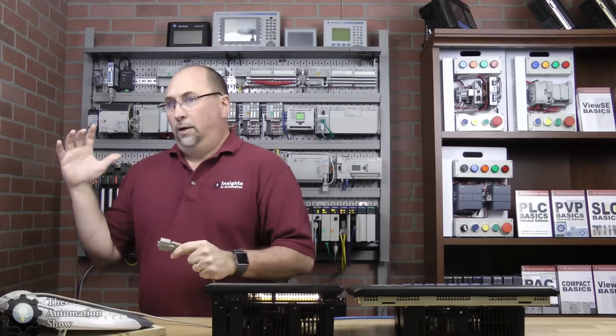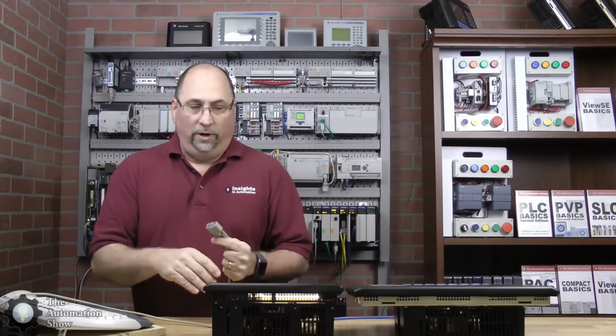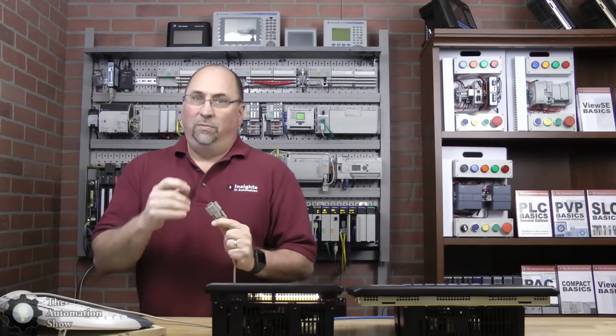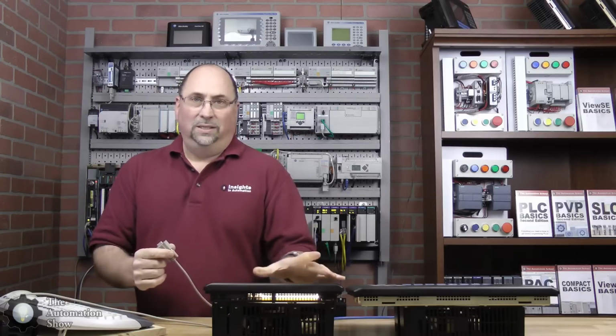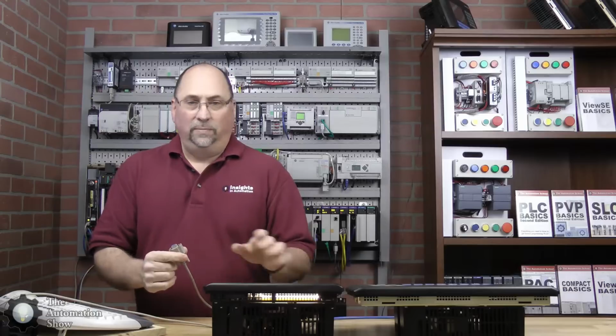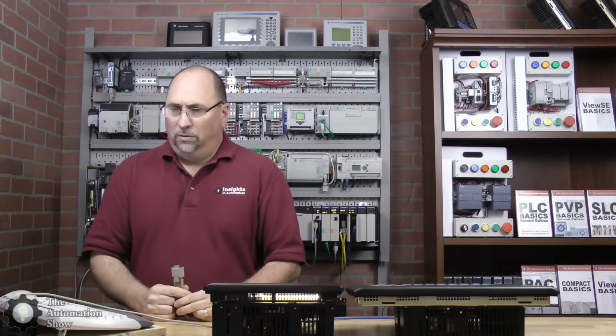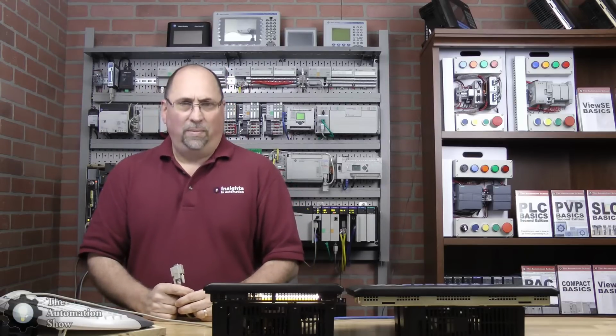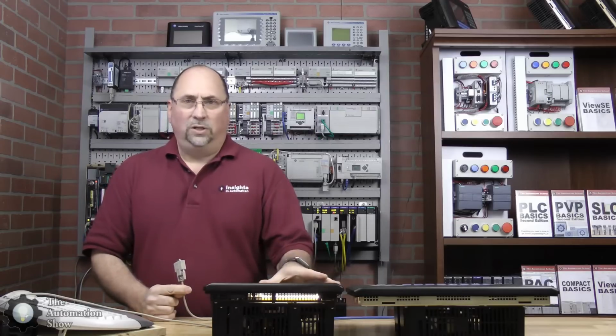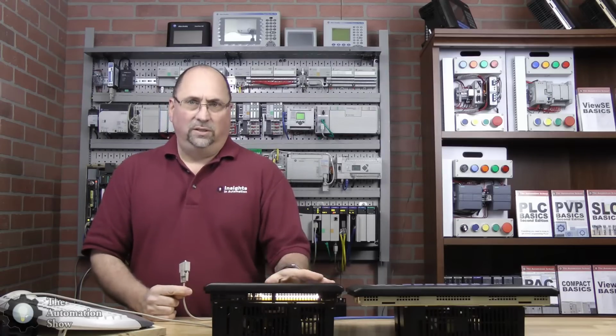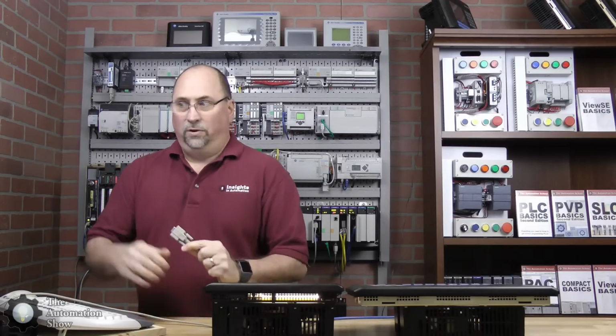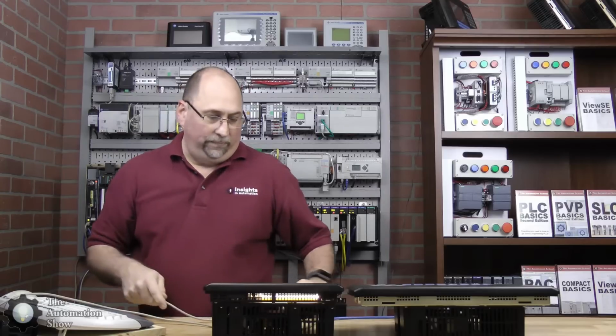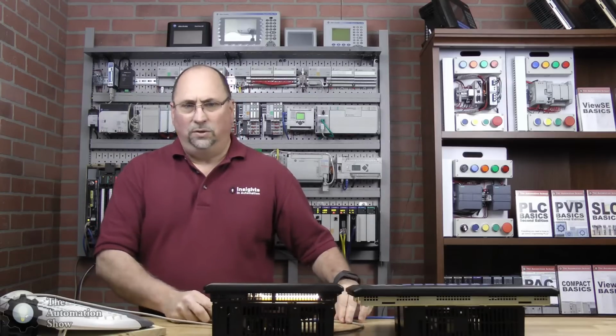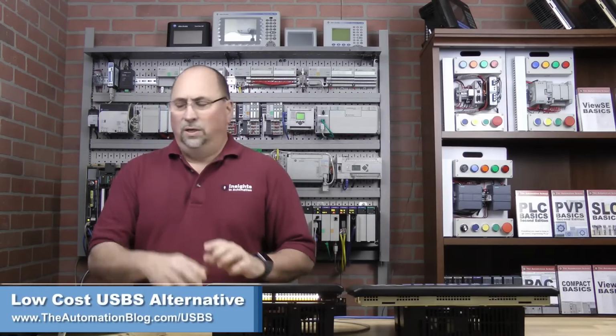But when you go PC to PanelView, 99.9% of every PanelView ever made by Rockwell is a DCE serial port device, okay? I think the only one that wasn't was maybe the PanelView Component, but all your standard PanelViews, PanelView Pluses, they're all DCE serial ports. So you need a straight through cable to go from your PC to your PanelView. And we'll be just doing DF1, so you could use a USB-to-serial adapter if you want to, etc.